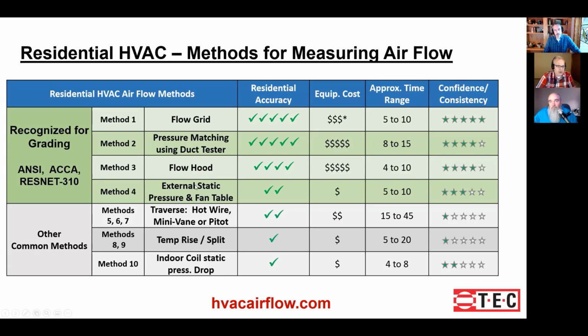Because what you're doing with the external static pressure and fan table is you're measuring a pressure drop across the components of the system. And that pressure drop across those components, it's the rise from the fan and whatever drop is included in either an evaporator coil or sometimes a secondary heat exchanger is part of the equation as well. And so as long as all those things are in the condition they left the factory, that's a good way to do it, and you'll get good repeatable results.